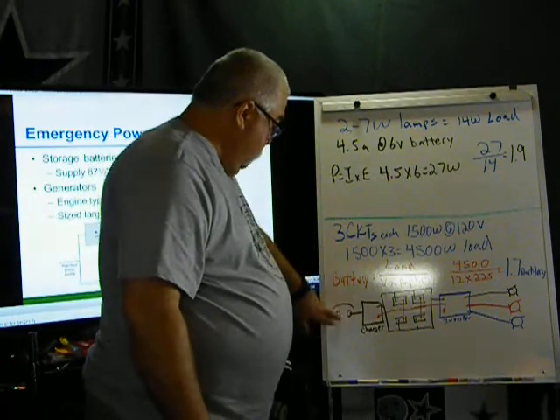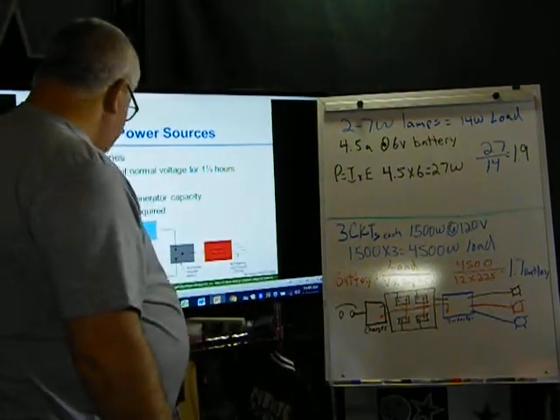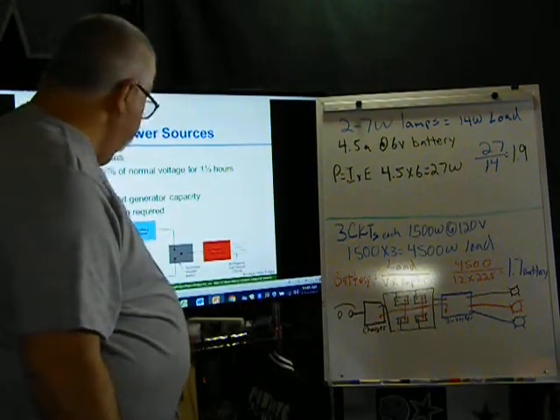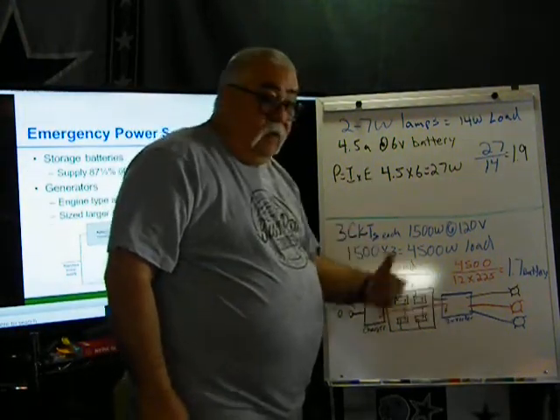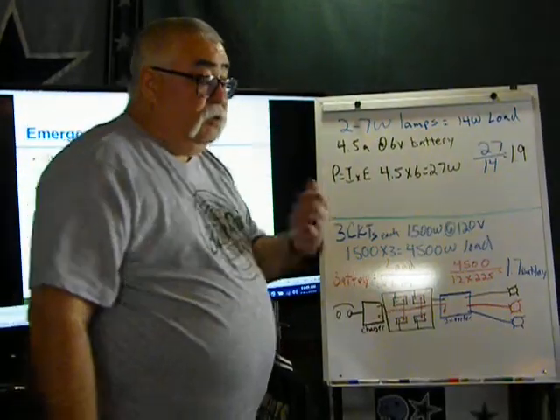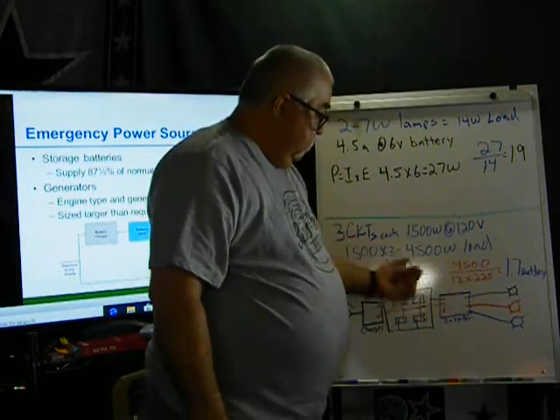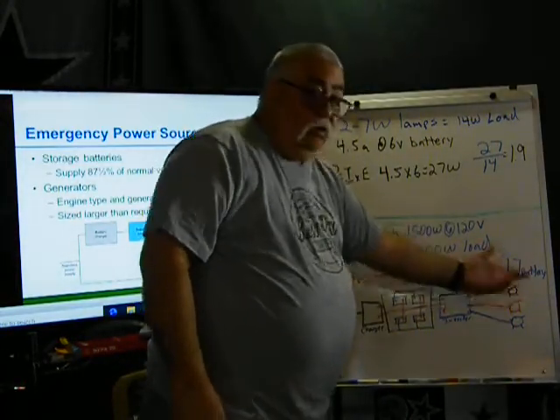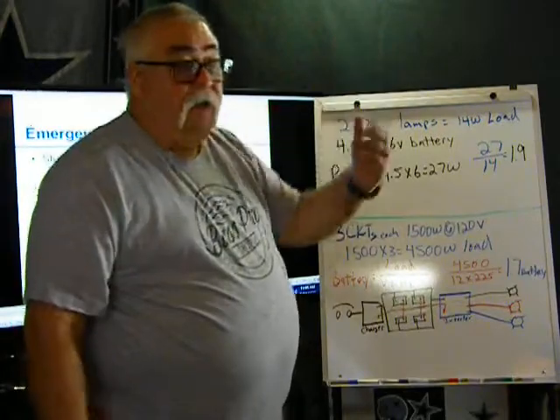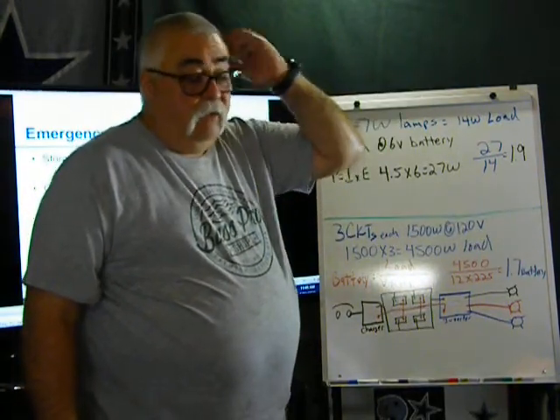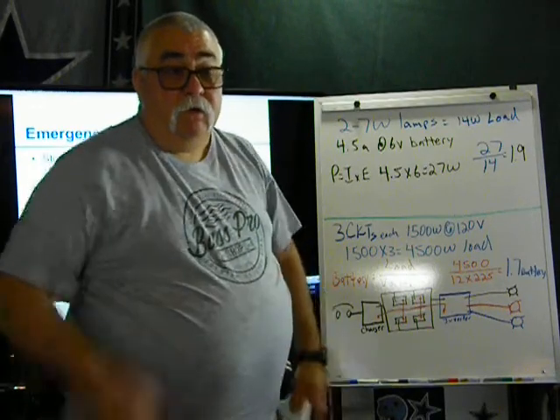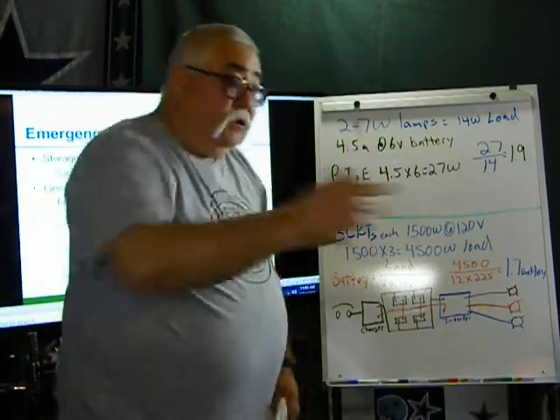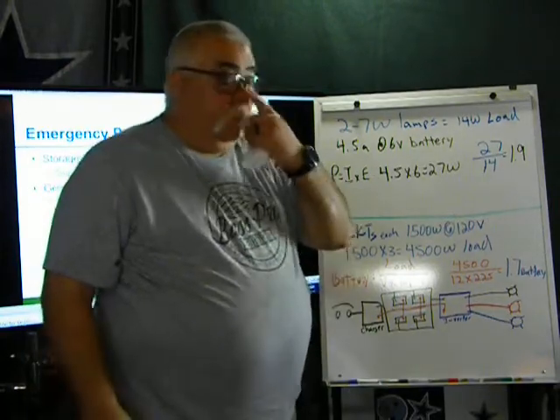So here's my source coming in. My standard source coming in. Goes to the charger, goes to the battery bank, then goes to an inverter because I'm running it at 120 volts. I'm not using DC, I'm running at 120 volts. So it goes to an inverter, the inverter changes it from DC to AC, and then it goes out and it feeds these lights. So let's say I got 3 floors and I got emergency lights on the first floor, emergency lights on the second floor, and I have emergency lights on the 3rd floor to light up the hallway, light up the stairwells so people can get out.